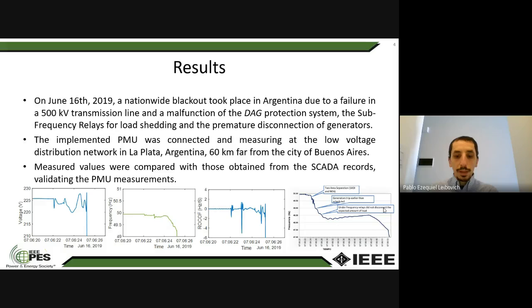During the failure, the implemented PMU was connected and measuring at the low voltage distribution network in La Plata, Argentina, 60 kilometers far from the city of Buenos Aires. In the figures are shown the direct sequence voltage amplitude, the frequency, and the RoCoF. It can be seen that an oscillation started at 7 a.m. and 6 minutes and continues during 3 seconds, when the blackout took place. Also, it can be analyzed that frequency dropped from nominal levels to values lower than 49.5 Hz before the blackout at the place where the PMU was installed, while RoCoF values detected were under -4 Hz per second. Measurements of the PMU were compared with those obtained from the SCADA records, validating the PMU.